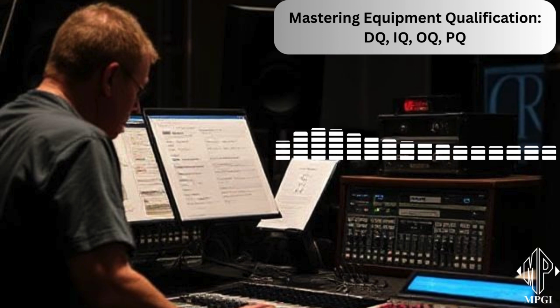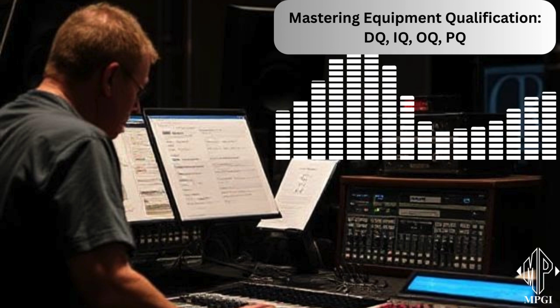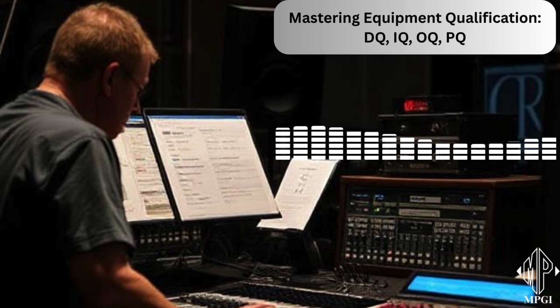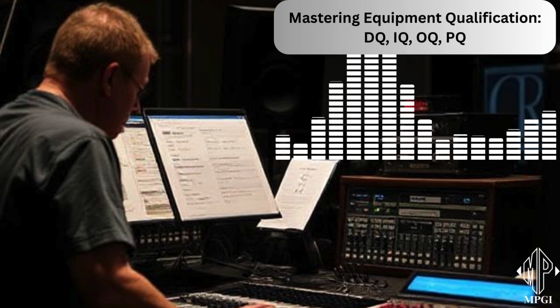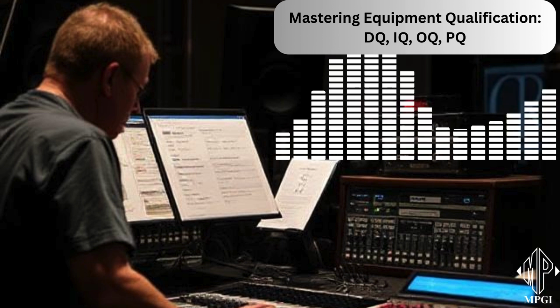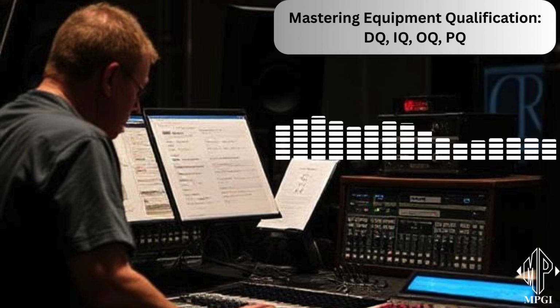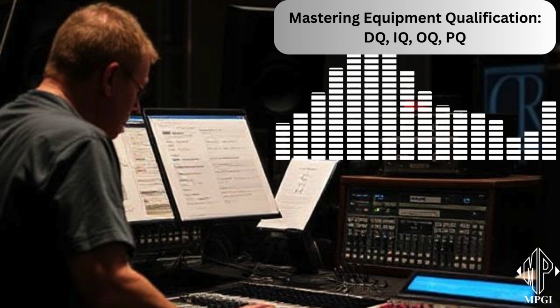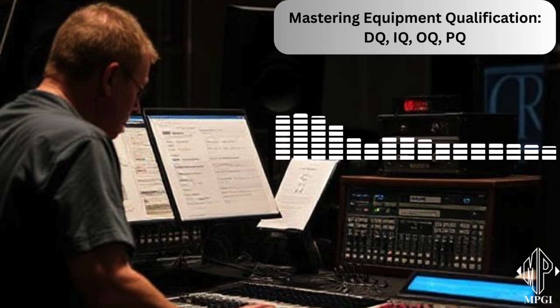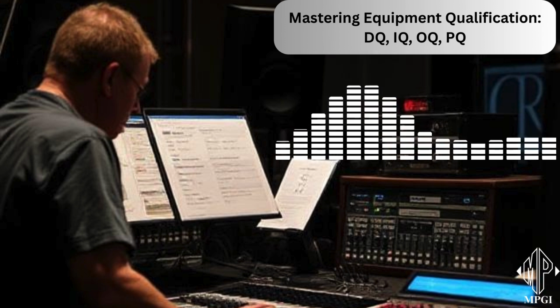Exactly. For medical devices, 21 CFR Part 820.70(g) says that equipment must meet its specified requirements and facilitate maintenance and cleaning. Again, key outcomes of the OQ testing. It seems like the regulations are really pushing for equipment that is not only functional, but also easy to keep clean and maintain. Right. And a key part of this is 21 CFR Part 820.75, which specifically identifies OQ as a vital part of ensuring equipment operates correctly within a validated manufacturing process. So OQ isn't just a nice to have, it's a regulatory requirement for demonstrating that the equipment can be consistently relied upon. Exactly. And the FDA guidance on process validation on FDA.gov underscores this, emphasizing that OQ is essential for reproducible commercial manufacturing. So it's all about ensuring consistency and reliability.